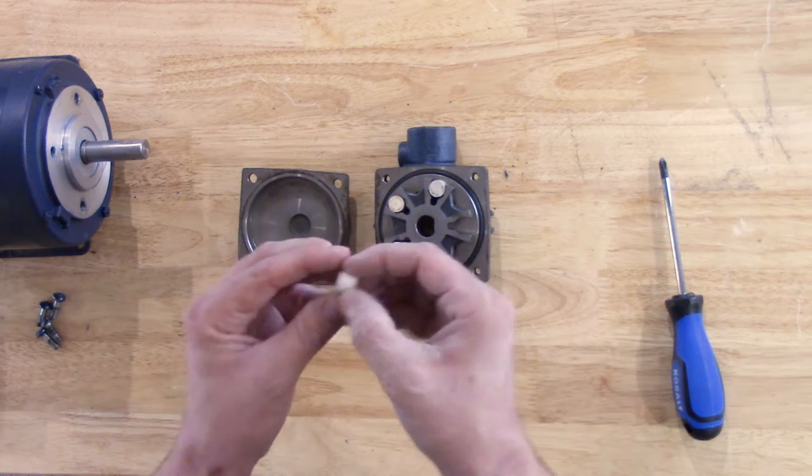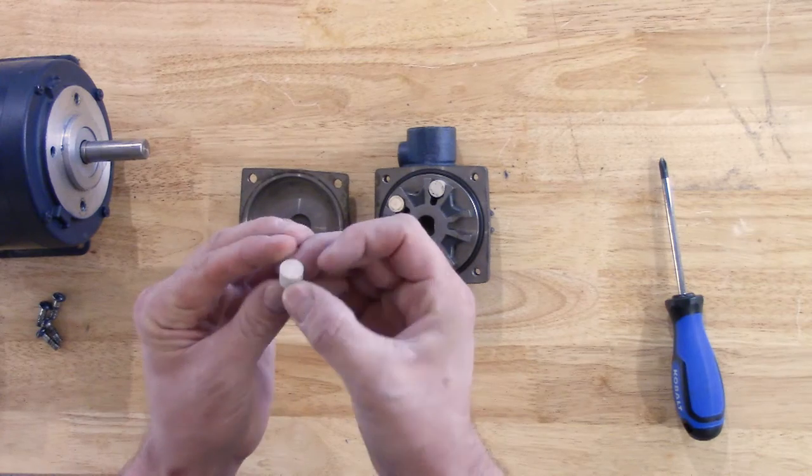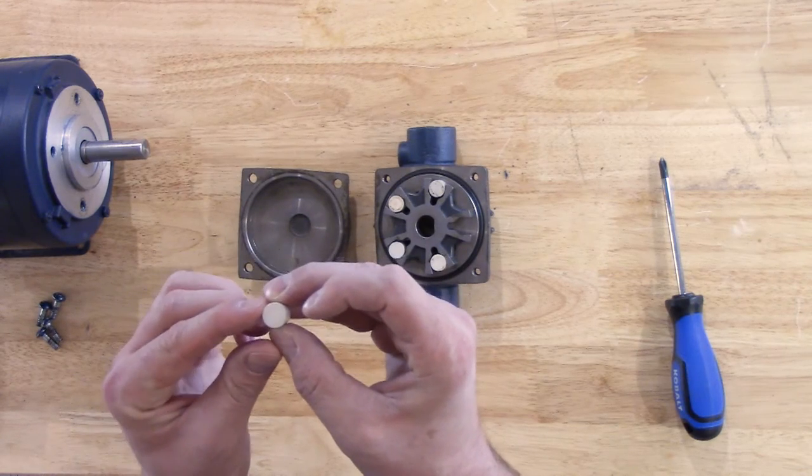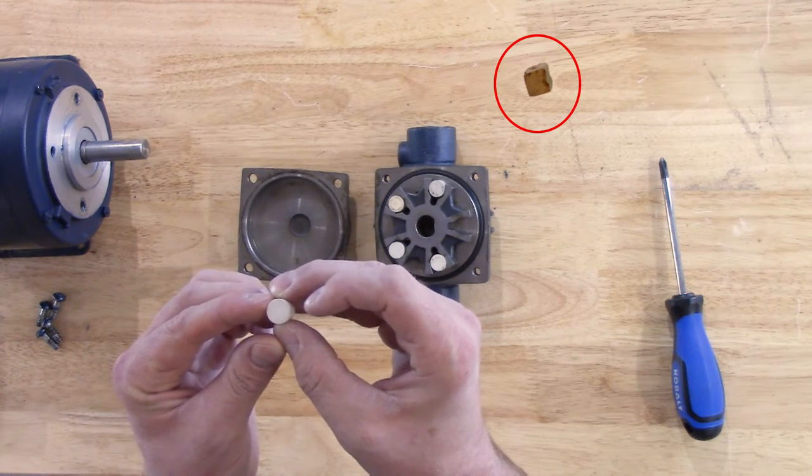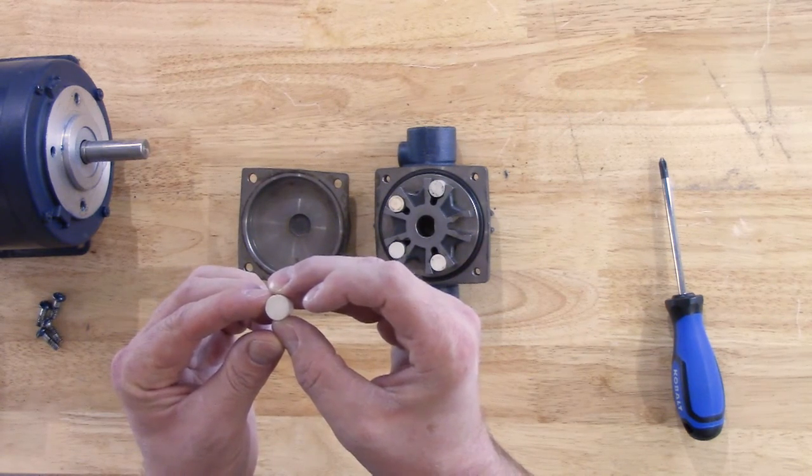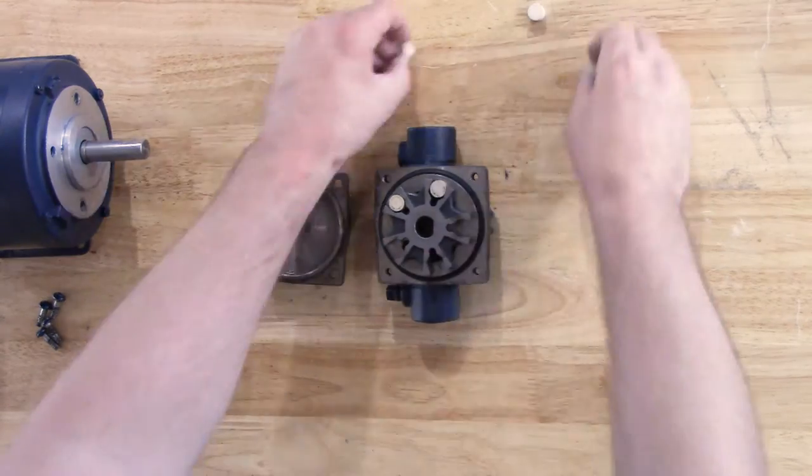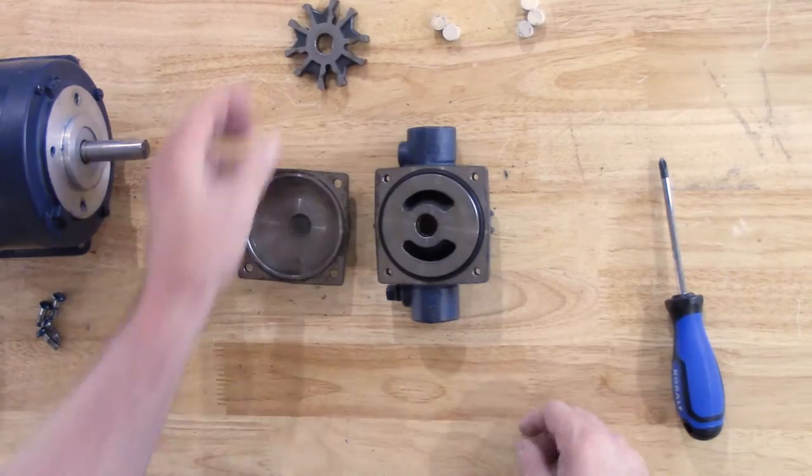Now we can see our Teflon rollers. This is a good time to inspect these rollers. Make sure that they are not flat spotted or undersized in any degree. If so, now is a good time to replace those. We'll set these off to the side for now, as well as our rotor.